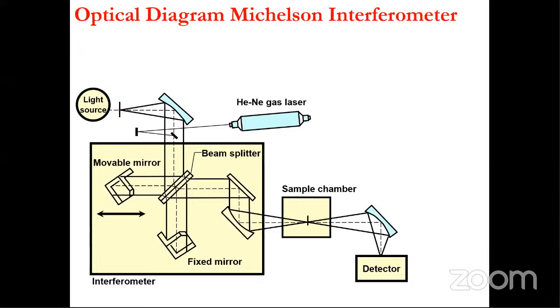Optics. We have a light source. We have one movable mirror and one fixed mirror, and the movable and fixed mirrors give you the multiple frequencies which are not superimposable, and then the beam is put into the sample chamber, and then we see it from the detector. So this is the path of how the light moves. It moves from the light source, then it is reflected and moves to the movable mirror, and it is again put to the beam splitter, then it goes to the sample chamber, and then the detector.